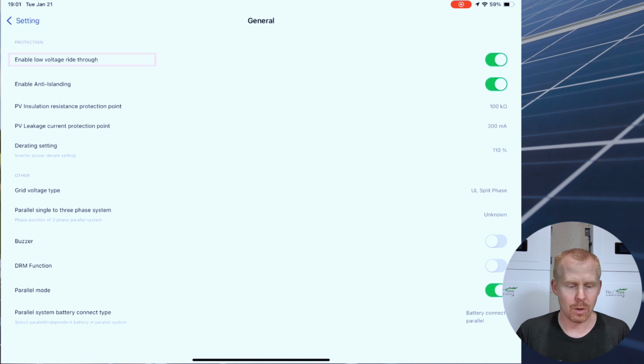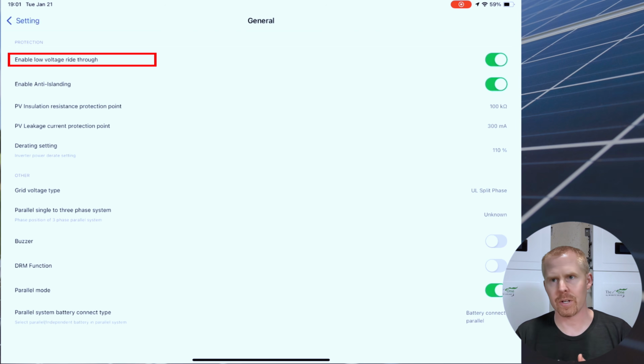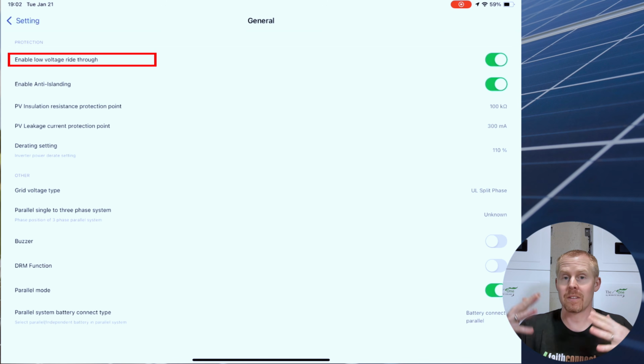Under the general section, low voltage ride through. So I think this is going to allow your inverter, if you have a large load and your voltage on your battery ends up sagging because of that large load, to handle that lower voltage from your battery a little bit longer than it would be able to normally. I think we saw this when I did the bounce house blower test, firing up multiple bounce house blowers on this inverter. The battery voltage actually does sag down, but the inverter allows that because this option is enabled. It kind of assumes that it's only going to sag for so long, like when a motor ramps up, and then the voltage is going to snap back up. So do you want to allow your inverter to try to handle that limited sag of battery voltage?